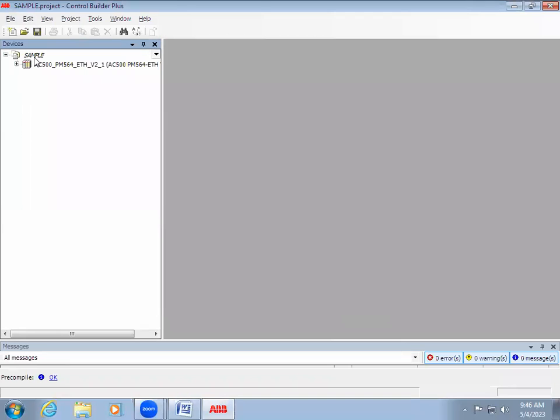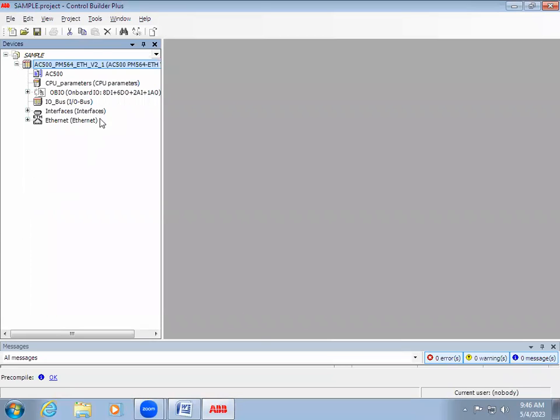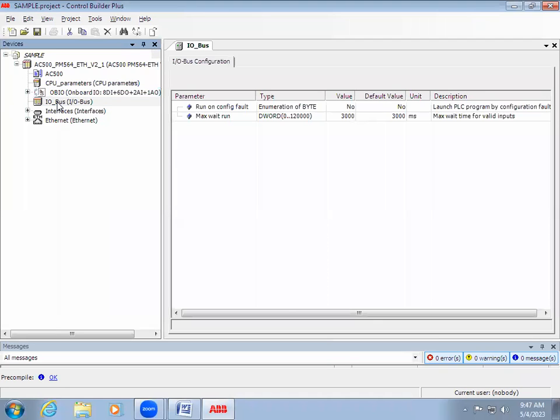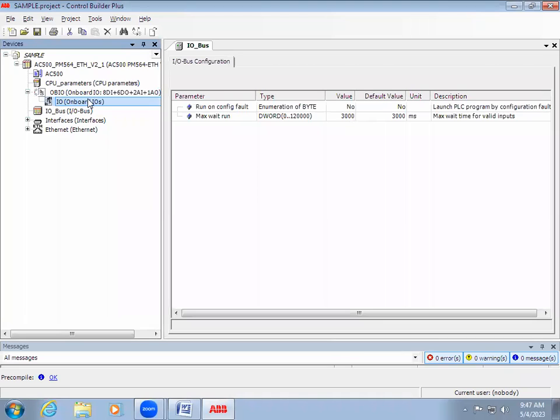You can see the project has been created and it's showing the model. If you expand it, you can see on the onboard we have eight digital inputs, six digital outputs, two analog inputs, and one analog output. That is the capacity of this board. If you want to configure the analog I/Os — whether voltage or current — you can expand the board and see the onboard I/Os. The I/O bus is for expansion modules, while the onboard I/Os are the built-in ones.